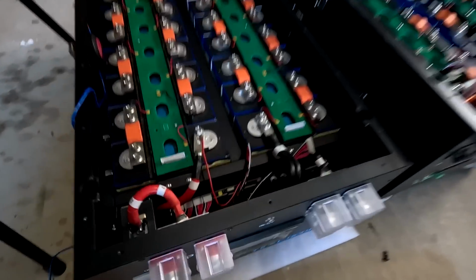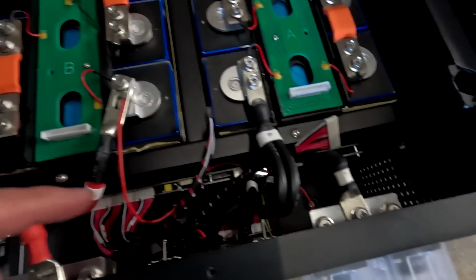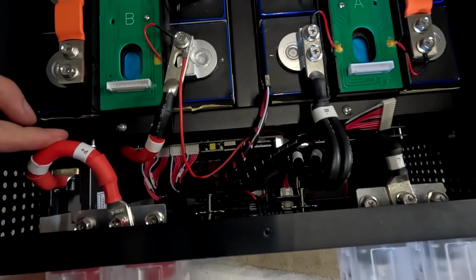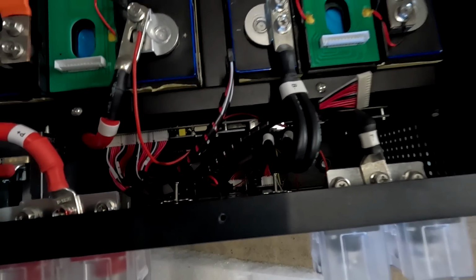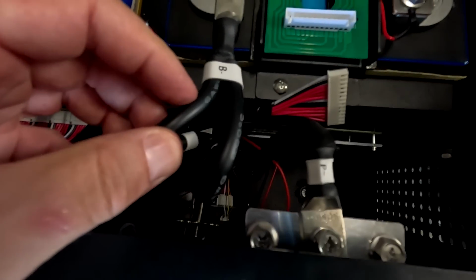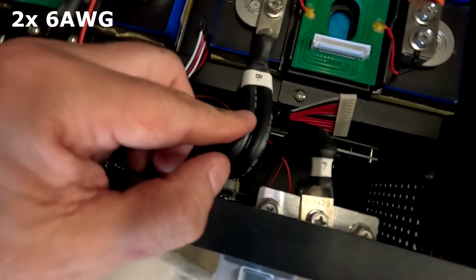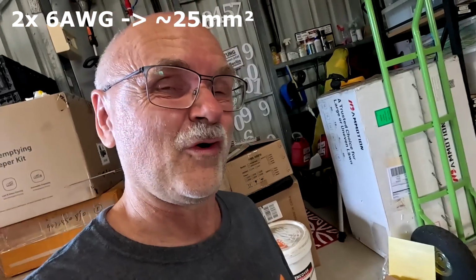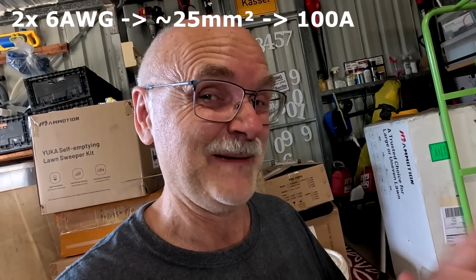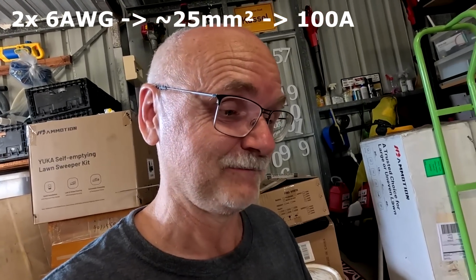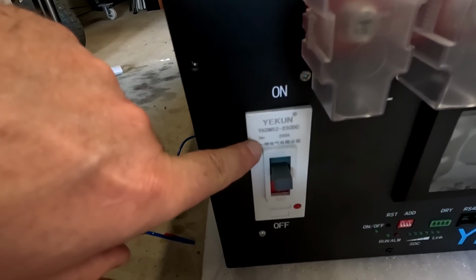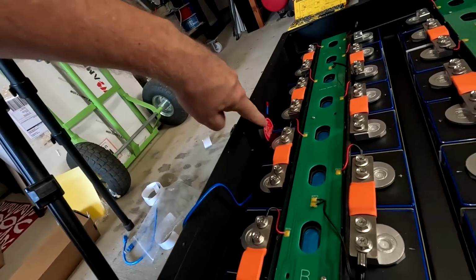So my friends, I've got everything connected so far. Well, we need to talk about the cable sizes used by Yixiang in these batteries. So let's start on this side here for the negative. They've got 6 gauge wire, 2 of them in parallel, which makes around 25 square millimeter cable. That is good for 97-100 amps max. Right? We have a 250 amp circuit breaker in here. So if we keep pushing 200 amps through these thin cables, we will need this fire extinguisher.